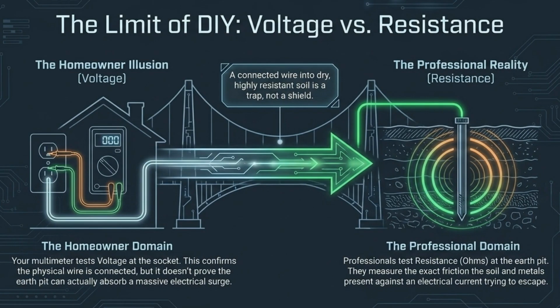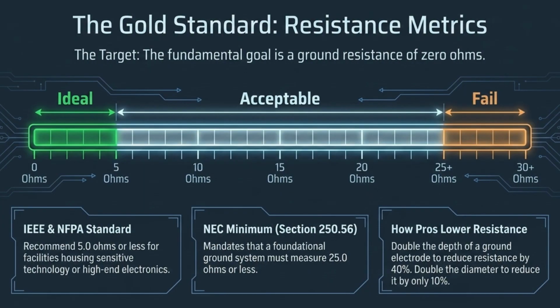It is important to understand the limits of DIY testing. Your multimeter measures voltage at the socket, confirming connectivity, but it cannot measure the true resistance at the earth pit. Only professional-grade equipment can provide that data. When considering resistance, standards like the IEEE recommend 5 ohms or less for sensitive electronics. The NEC generally sets a limit of 25 ohms for ground systems. Lowering resistance is best achieved by increasing the depth of the electrode.